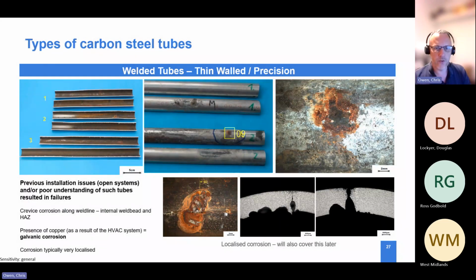Just a quick case study about thin wall, to highlight some issues we've had when pipework isn't installed correctly. We manufacture a lot of this thin wall product, used in Germany for example with no issues whatsoever. In the UK it had problems, mainly because it's meant to be for closed systems with no oxygen, but we saw it being used in systems with oxygen, and also in systems with other, dissimilar materials and metals, which brings us to galvanic corrosion, which we'll talk about a little bit later on.